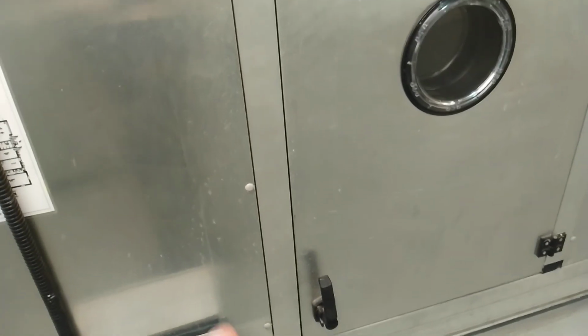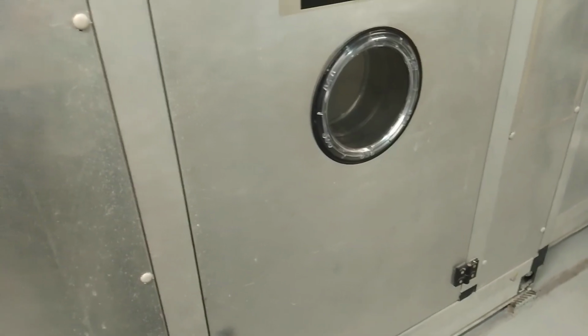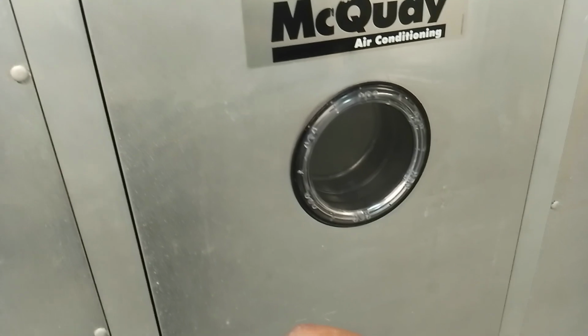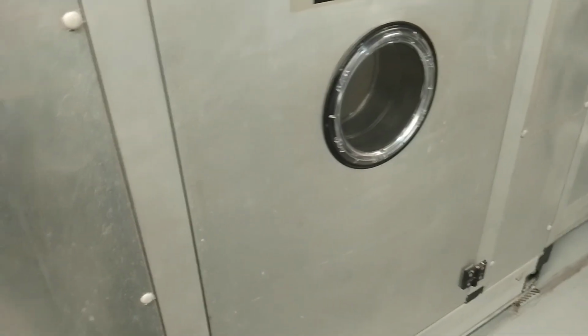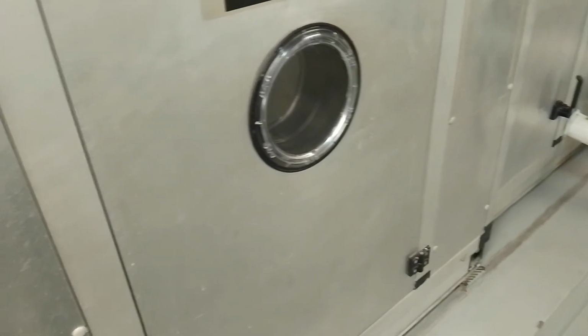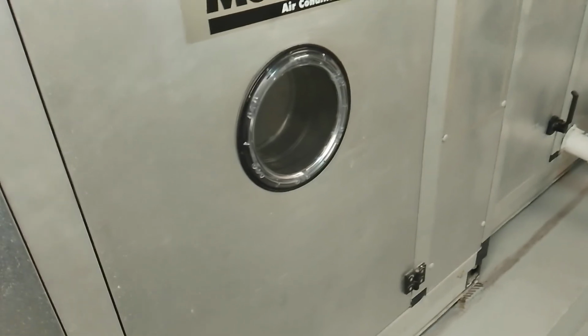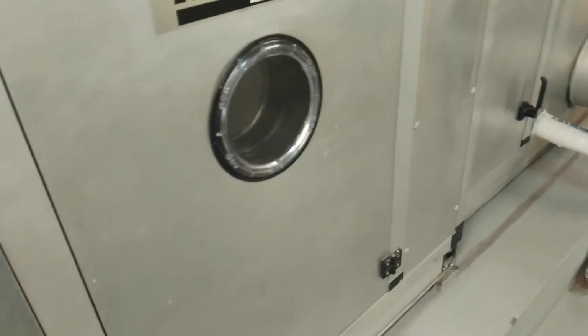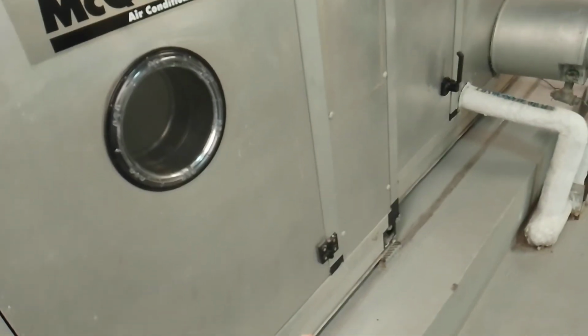Then after it reaches the room, we have in the room, as I told you, a damper also, and we have also a VAV, whereby the air is regulated to a certain temperature according to the setting of the one who is using the room. That's how our AHU works.